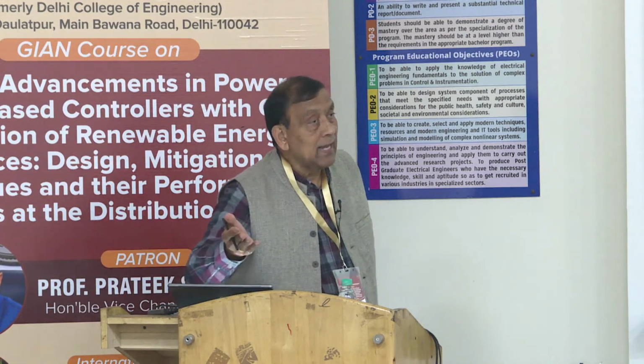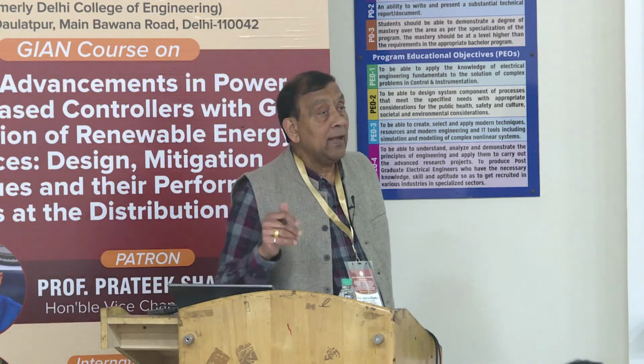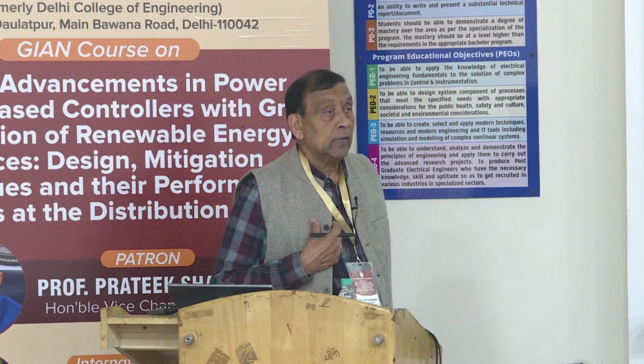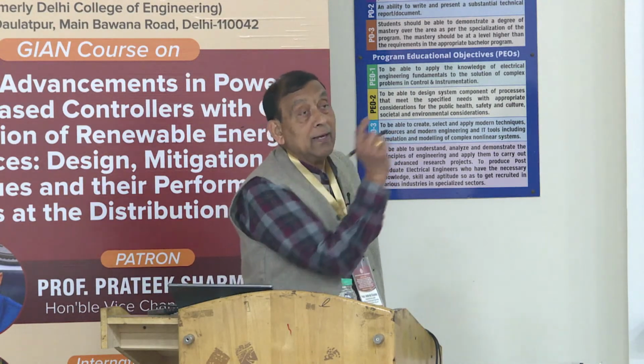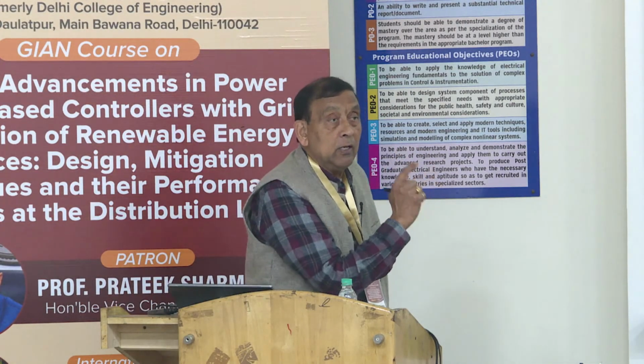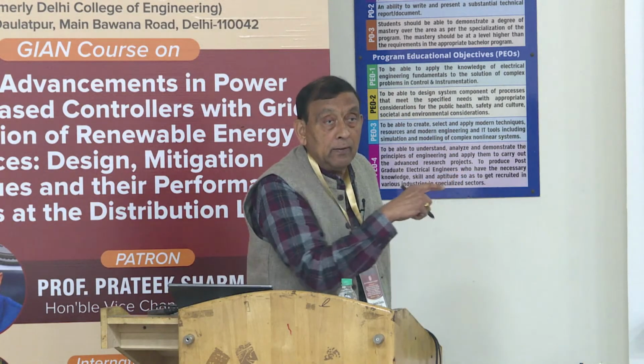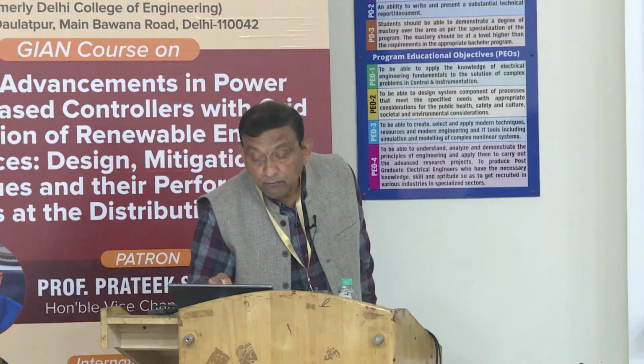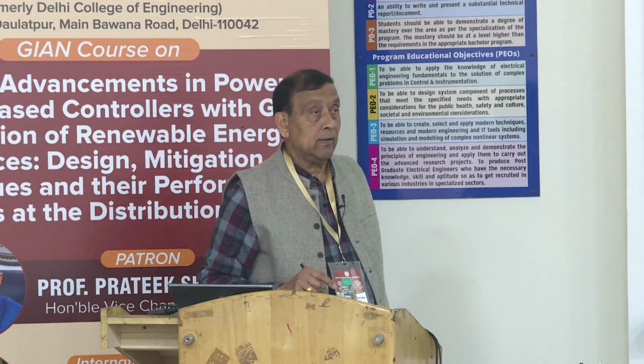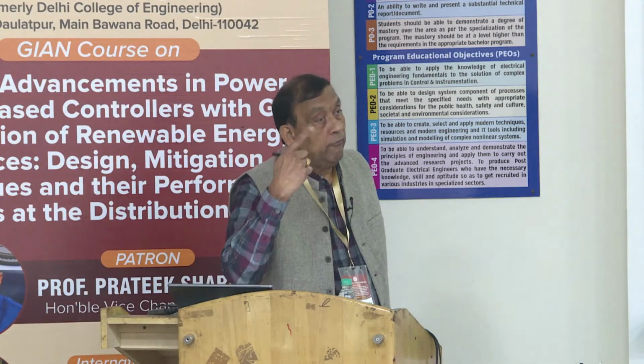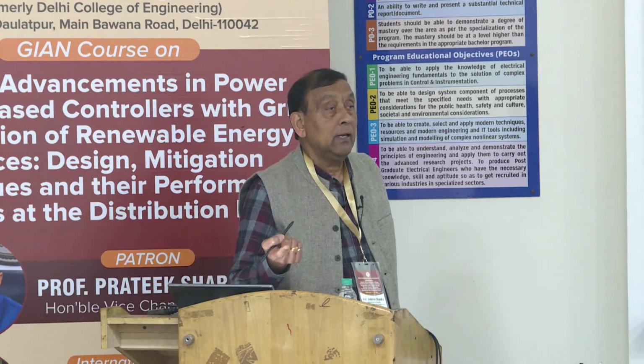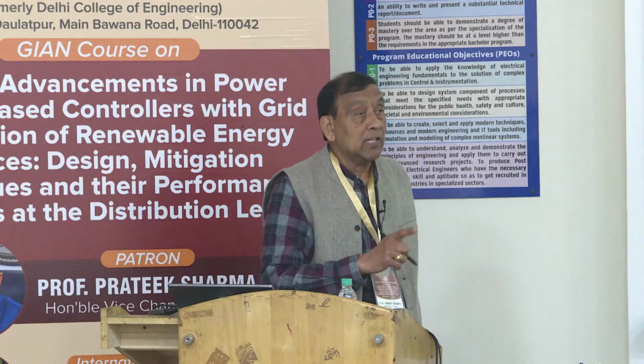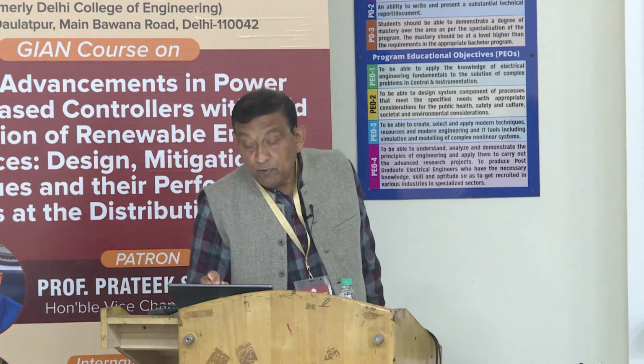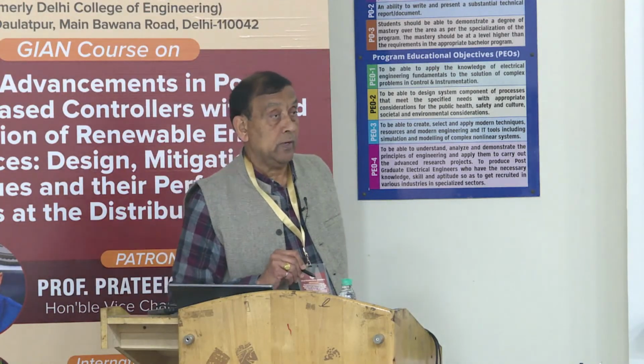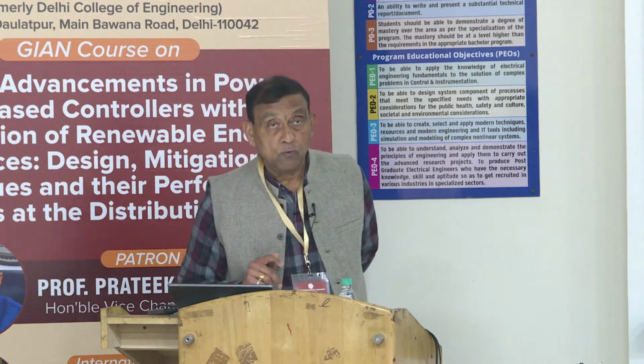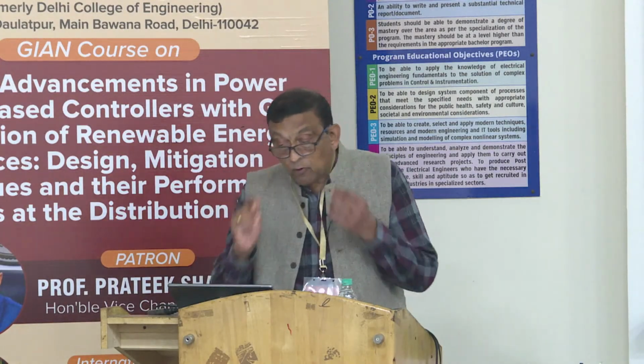So in the secondary side load, if it is generating seventh harmonic current, so when it will go other side, primary side of the transformer to the network, then the seventh harmonic will have phase shift of minus 30 degree. And fifth harmonic is a negative sequence. When it goes to the primary side of the transformer to the network, it will get plus 30 degree phase shift. So this is very important to know. Later on we will use this technique for harmonic cancellation.